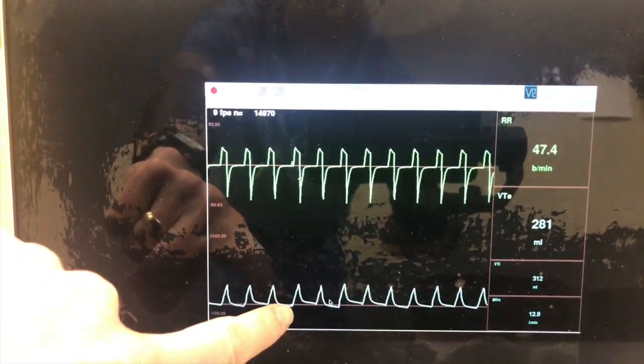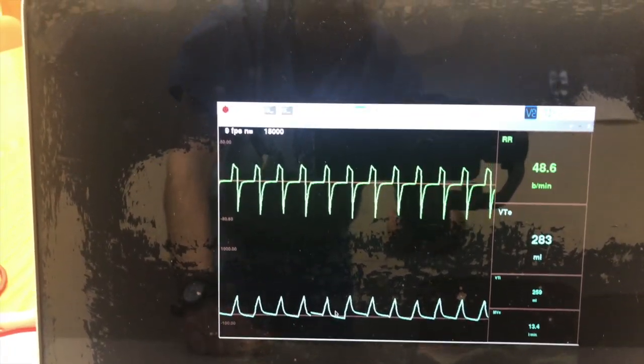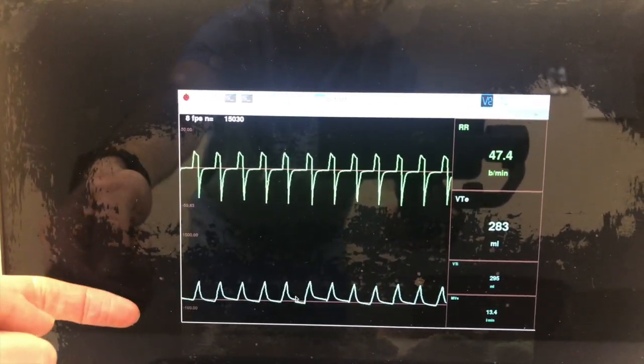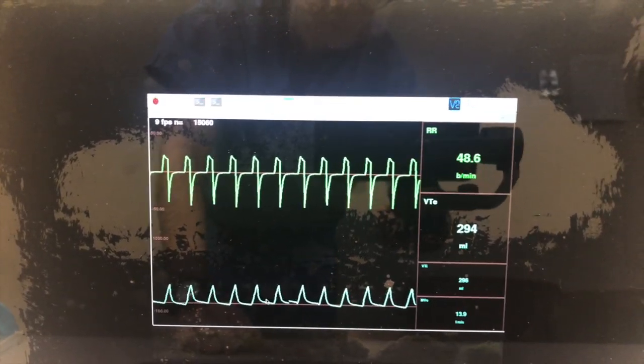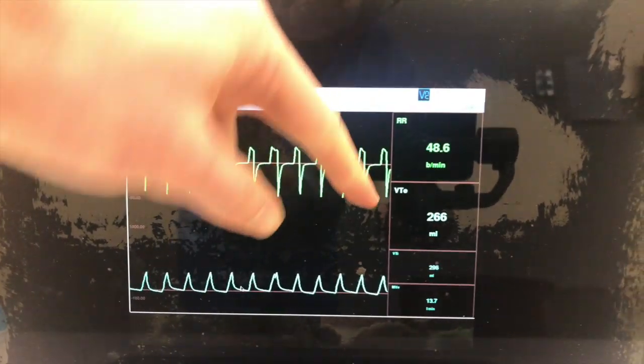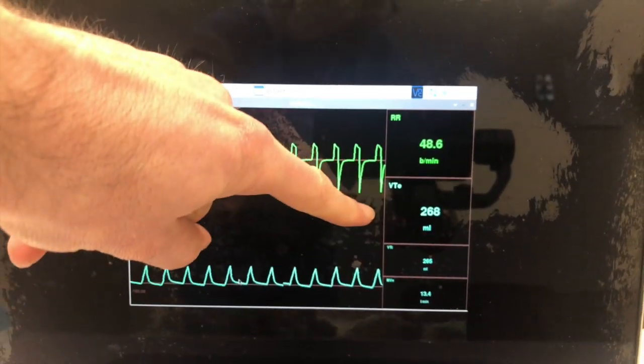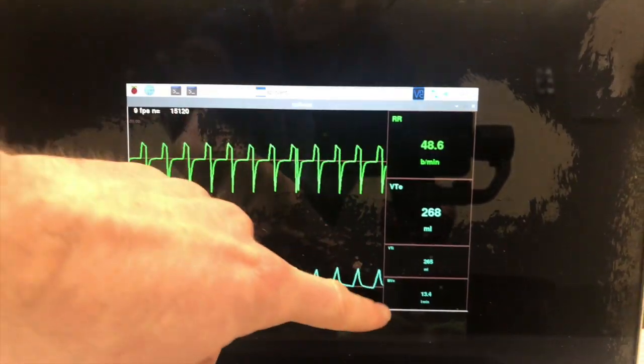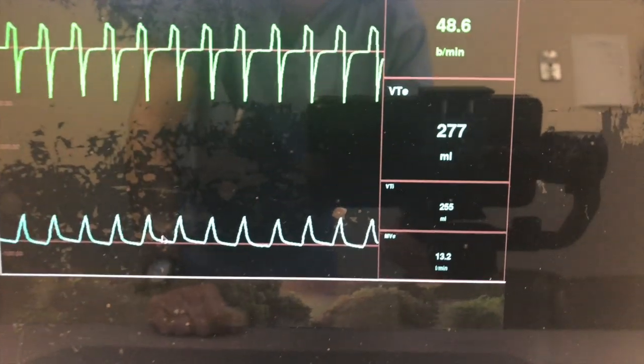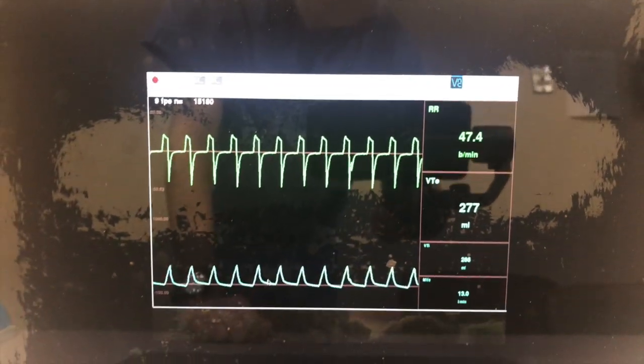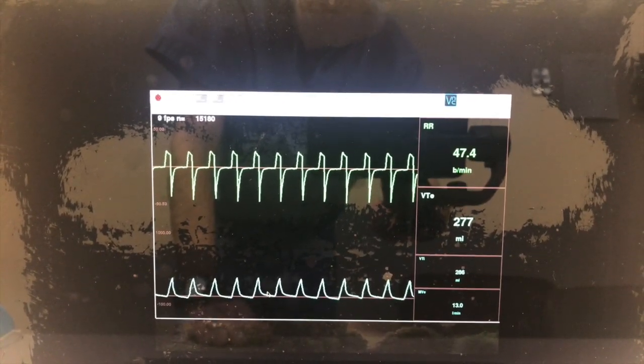You can see that this is updating in real time in the same way that you would get from an actual vent screen. On the top is the flow curve, and then down on the second graph there is the volume curve. Over on the right, we've got respiratory rate, inspiratory and expiratory tidal volumes, and then a calculated minute ventilation as well. The next step here will be to add a pressure curve onto this as well.